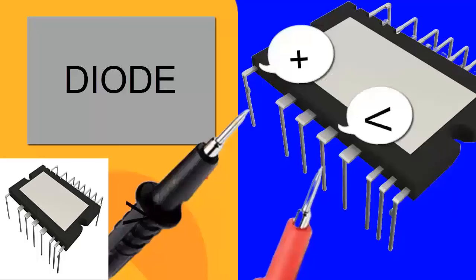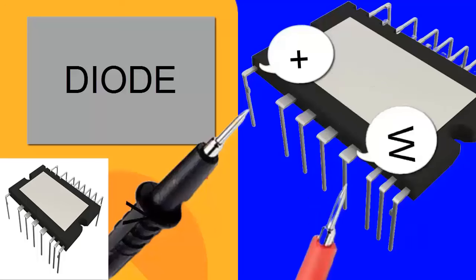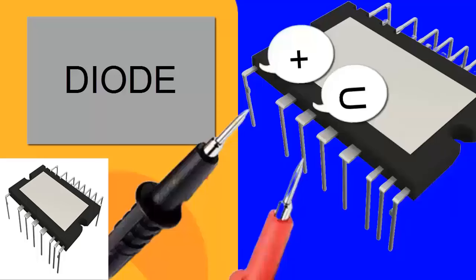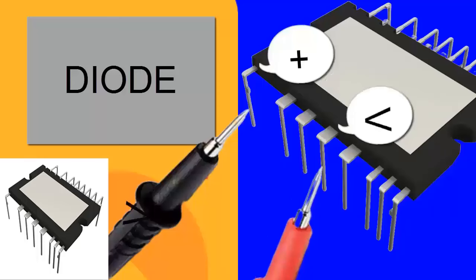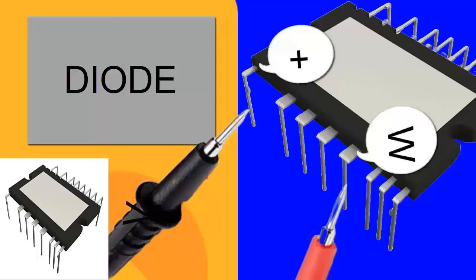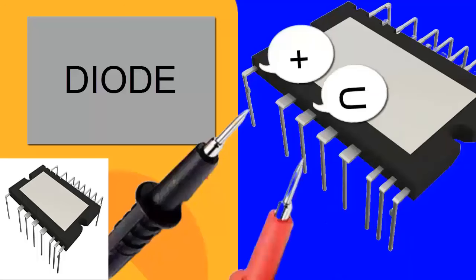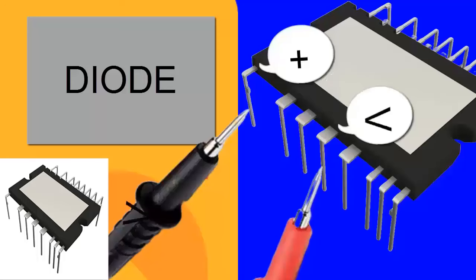Now, using the identified IPM terminals, place the black probe of the multimeter on the positive pin of the IPM. Then place the red probe on the U, V, and W terminals sequentially. The readings should be consistent, with similar values across all three terminals U, V, and W. Any significant variation could indicate a problem with the IPM module.